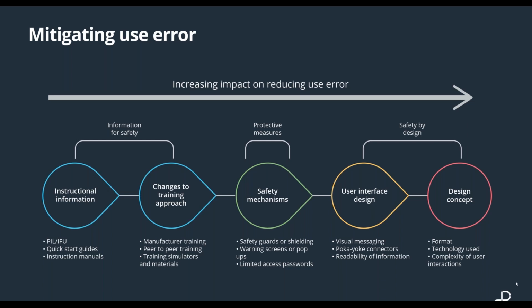However, while it doesn't affect use risk and regulatory risk for the company, there is commercial risk in poor user experiences. So while there might be some recommendations that come back from a formative which are not to do with risk, if you think people will not choose your device because of that problem with the user interface, then there's at least a conversation to be had about the value of taking a step back and making tweaks to the user interface, even if it delays launch.